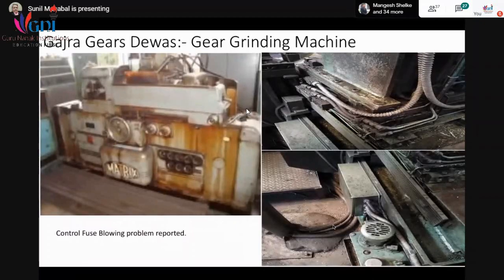So then I took permission from the production department that I wanted the operator to run the machine and we would be circling the machine. Like they surround the villain from all sides in a movie. So the entire maintenance team was around the machine, and I allotted the job to every single person: you will look only at this conduit, nothing else. You will see only this conduit and the opening of the conduit in the panel. So one person was sitting, keeping the panel open and observing the openings of the conduits, and other fellows were standing in front of the different conduits.